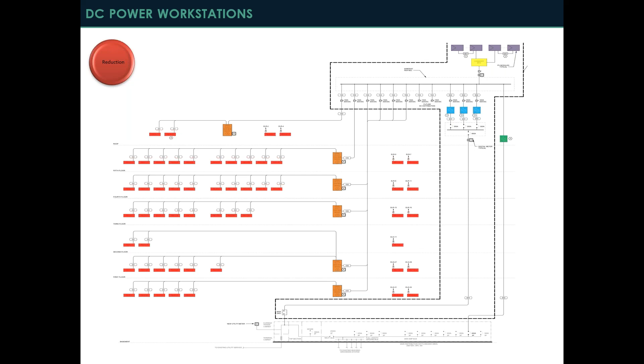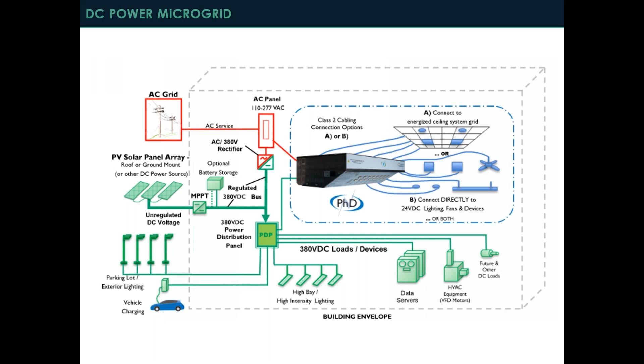Each of those red boxes represents an above-ceiling power hub distributed through the building. This power hub can take AC power from the power grid during times when it's dark, rainy, or snowy and there's no sunlight. Then when the sun is out and the PV array is generating power, it can accept that DC power directly into the power hub, and again distribute DC power throughout the space.